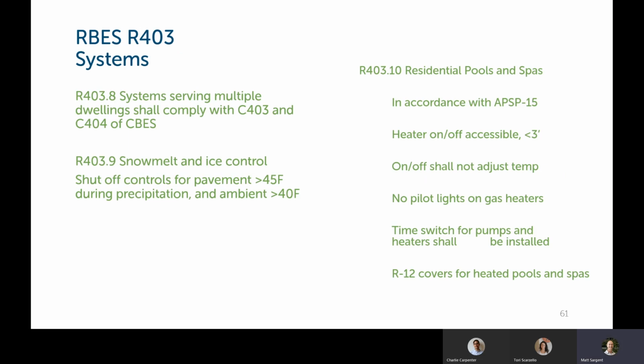Systems serving multiple dwellings have to comply with C403 and C404 of CBES. So this would be like in a multifamily system. We're using CBES code for that. There's a snow melt and ice control stipulation. So for pavement greater than 45 degrees during precipitation and the ambient greater than 40 degrees, we need to have a control that will shut off snow melt and ice control.